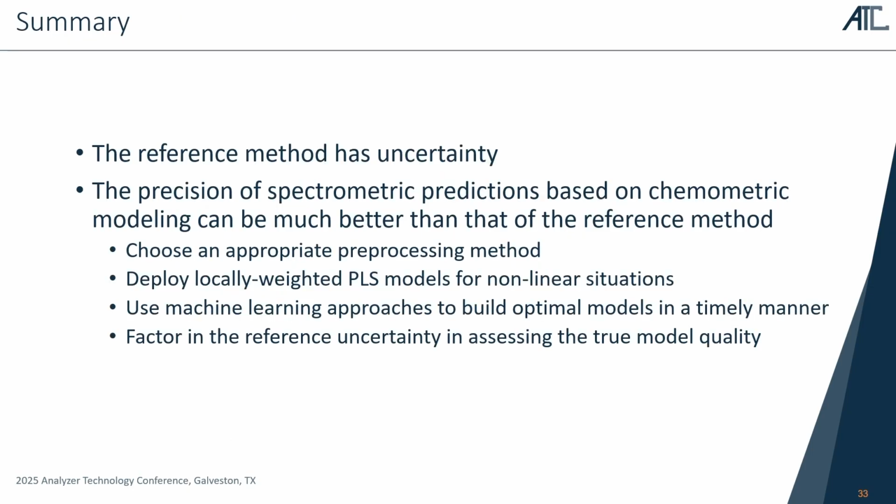So the end of this is, just keep in mind that the reference value has uncertainty. It is not a precise number. It is something that you can handle by running it a whole bunch of times, but no one ever does that. But we essentially have the power of multiple samples by running a bunch of different samples, even if they're getting different reference values. And using that information, you can tune in onto what the true error in your system is.